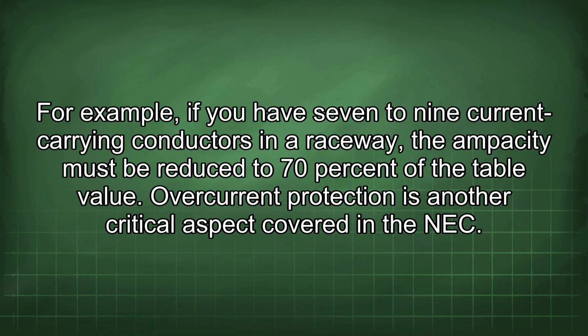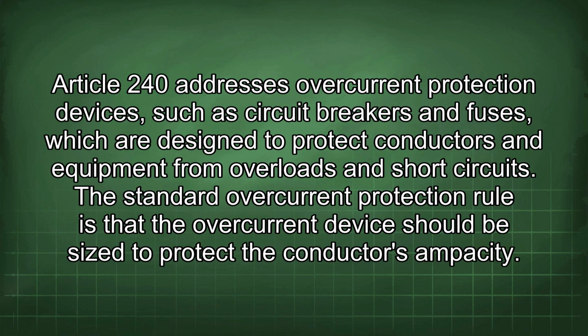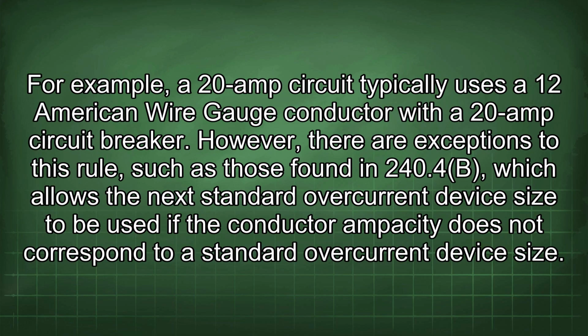of the table value. Overcurrent protection is another critical aspect covered in the NEC. Article 240 addresses overcurrent protection devices such as circuit breakers and fuses, which are designed to protect conductors and equipment from overloads and short circuits. The standard overcurrent protection rule is that the overcurrent device should be sized to protect the conductor's ampacity. For example, a 20 amp circuit typically uses a 12 American wire gauge conductor with a 20 amp circuit breaker. However, there are exceptions to this rule, such as those found in 240.4(B), which allows the next standard overcurrent device size to be used if the conductor ampacity does not correspond to a standard overcurrent device size.